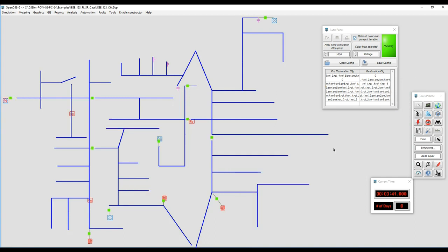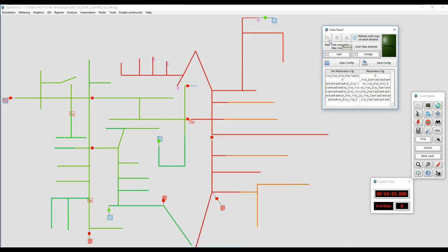You can see the system reacts and it's going to try to restore the voltage. And we have recovered zones 1, 2, and 3. We can see where the fault was applied. Everything seems to be working fine. Again, this is not a smart algorithm, it's just following a file. So we're going to clear everything and take it back to normal. And again, the regulators start acting and taking everything back into the reasonable range.